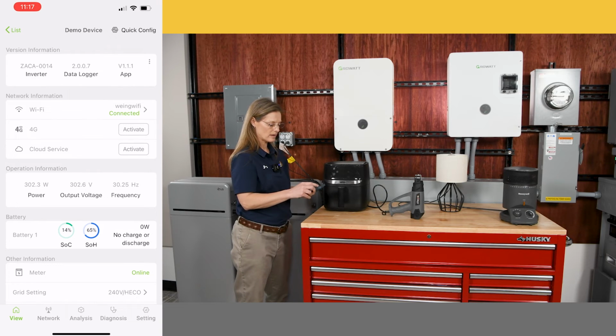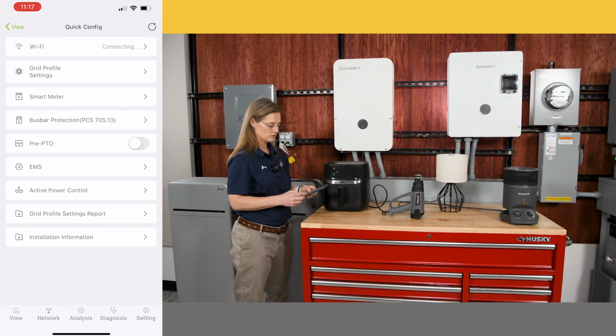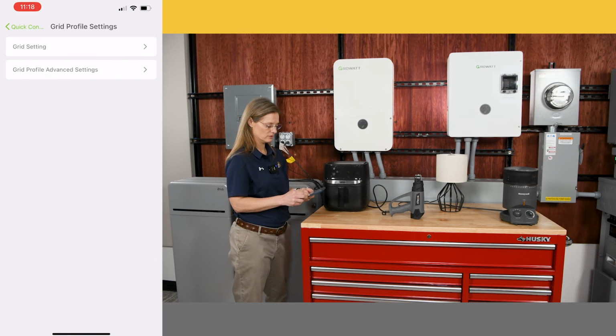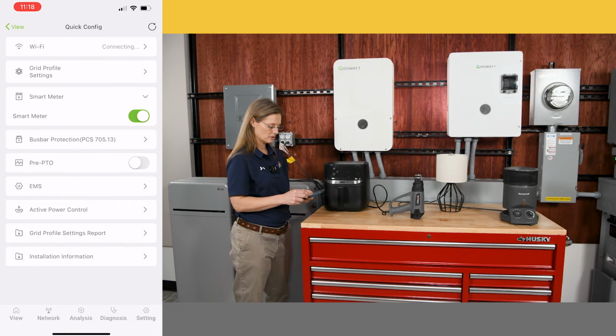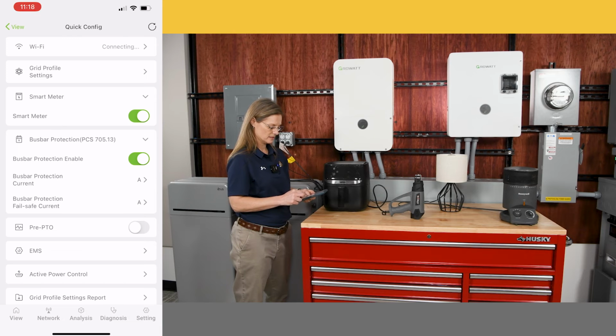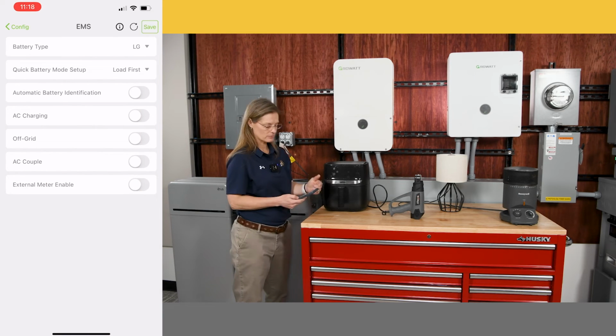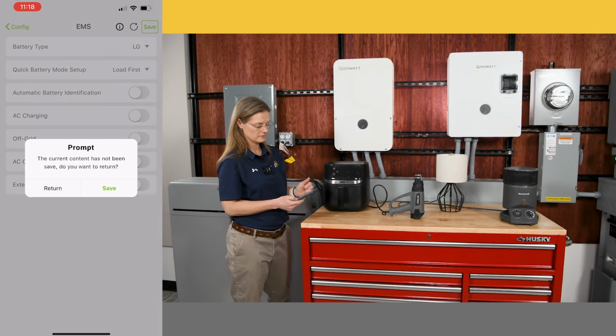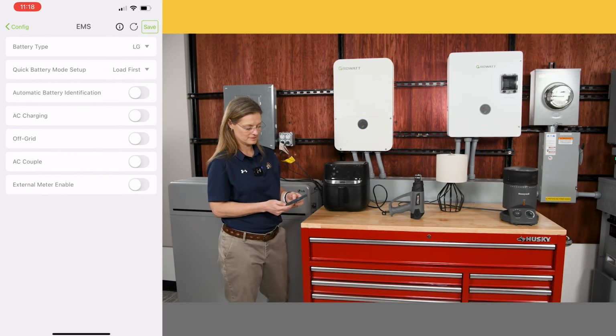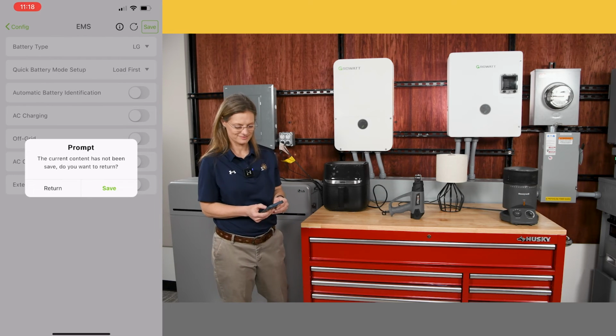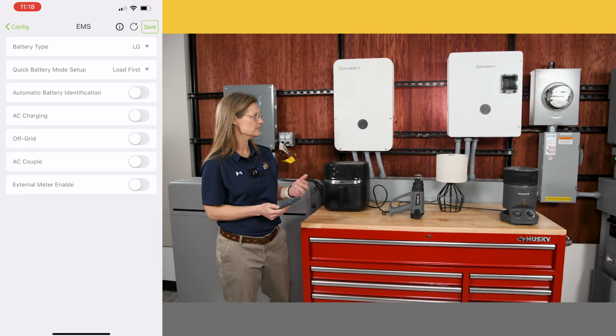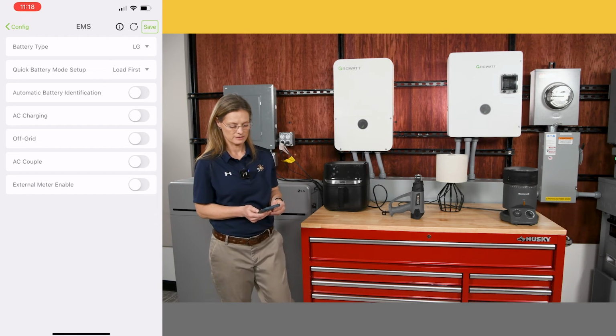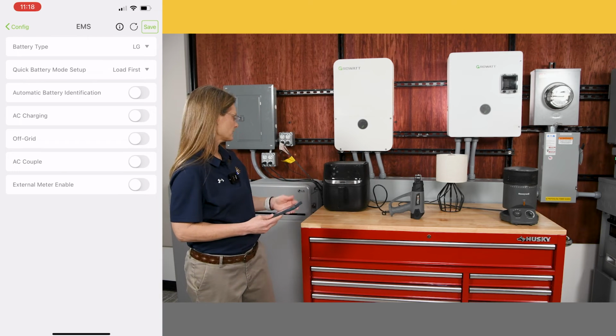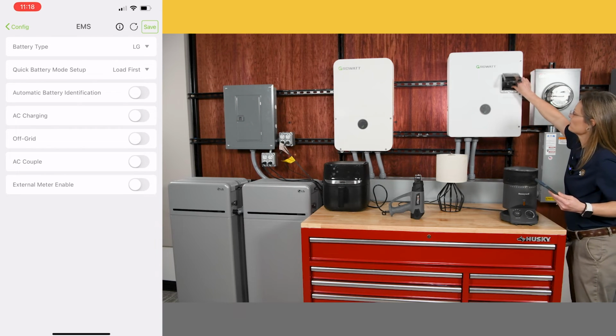You may need to go to the top right where it says Quick Config, as you did in the other app, and put in some of those things that you did in ShineTools and configure the grid setting. And enable your smart meter and do some of the other things as you did in ShineTools as well. Right now, it is not reading any of our preconfigured settings because we don't actually have our inverter on. So we need to turn on our grid to give our inverter power so that we can show you all of the settings that would automatically be read by our app. We'll go ahead and give our inverter power.